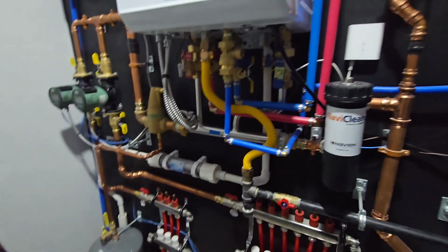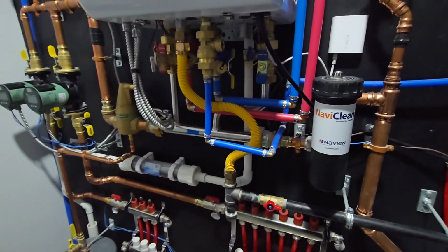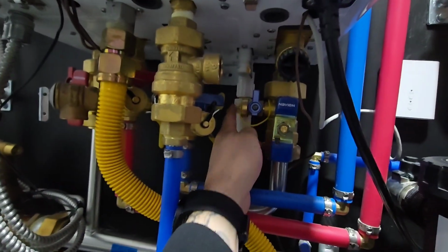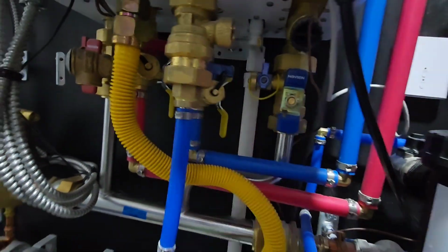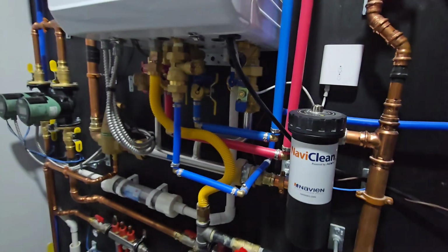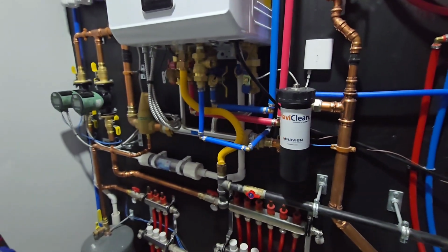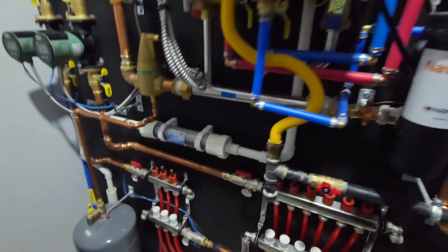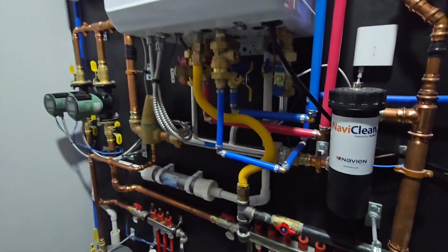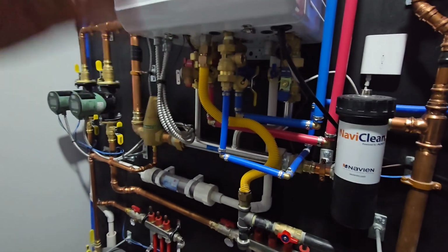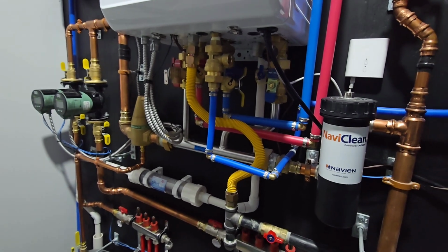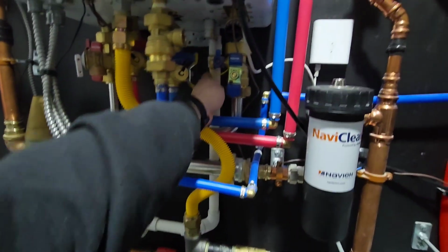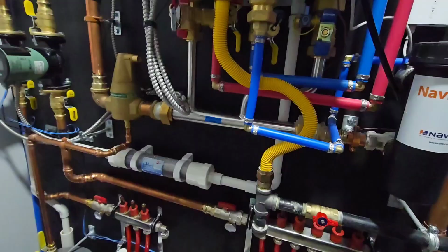So when a boiler is condensing, you have to do something with that leftover condensation. So on this unit right here, it's going to be dripping right out of this port back there. And there's many things you can do with that depending on your situation. So the first thing you're going to want to do is run it through a neutralizer. That condensation, because it's being burnt from fuel, there's carbon dioxide in it, it's going to be highly acidic. So what's going to be dripping directly out of that is a very high acidity level water.